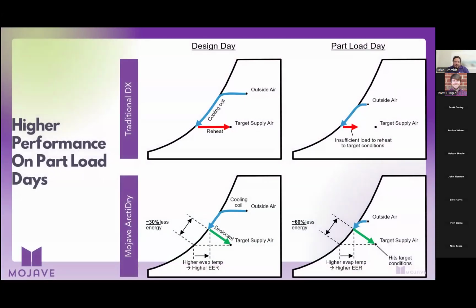In part load days, we can see this even more. So up above, we have the traditional DX system in design day, the same thing I just went through. And in part load day, sometimes we have insufficient load to reheat to target conditions. So we can see it not reheating to space neutral conditions, providing space temperatures that are too low, and also the compressor going on and off throughout the day.